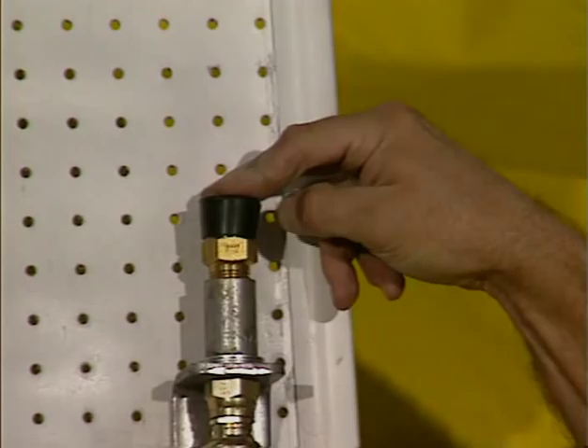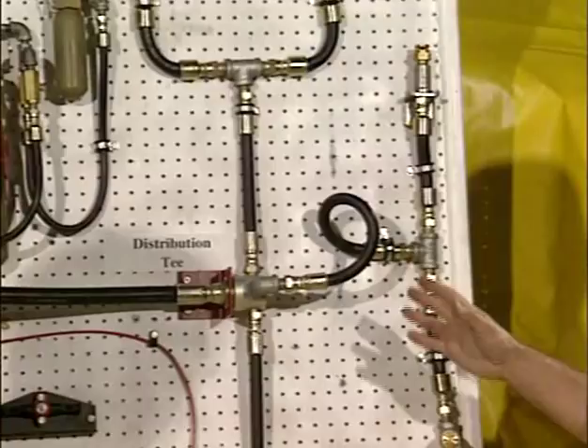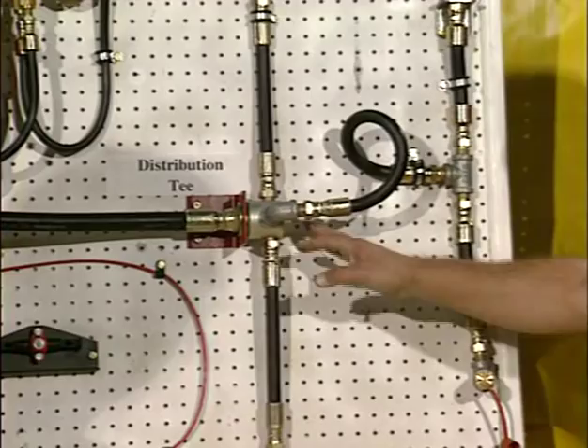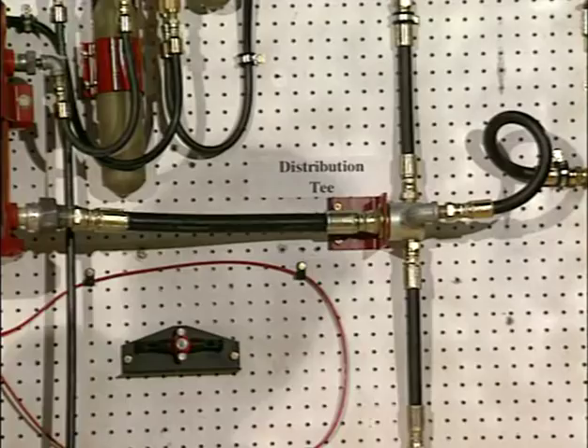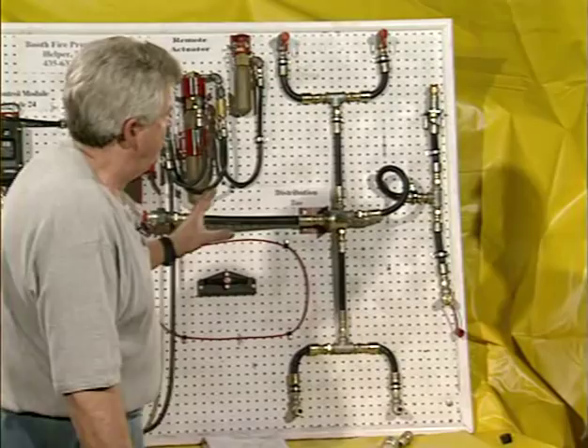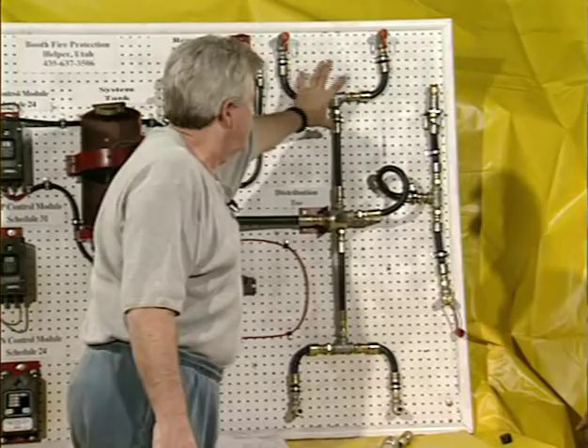Under the new rule, the system must be sealed at the nozzles to prevent moisture, dirt, and debris from entering. As for maximum distances: on a 20-pound or 30-pound system, you can go 40 feet on the supply line, and from the distribution to the nozzle is 18 feet maximum. The hoses between groups don't have to be the same length, but this group, this group, and that group have to be within a three-to-one ratio of one another.